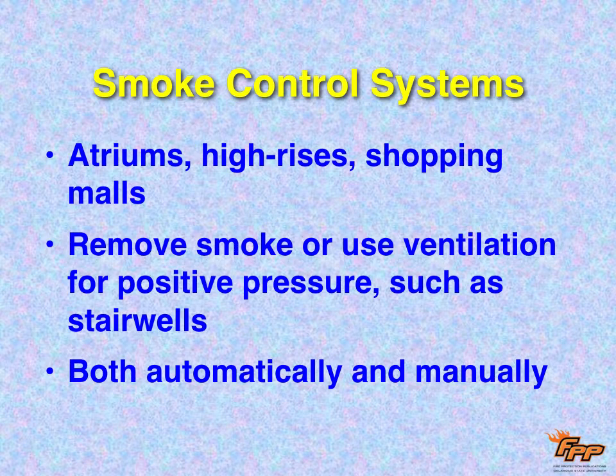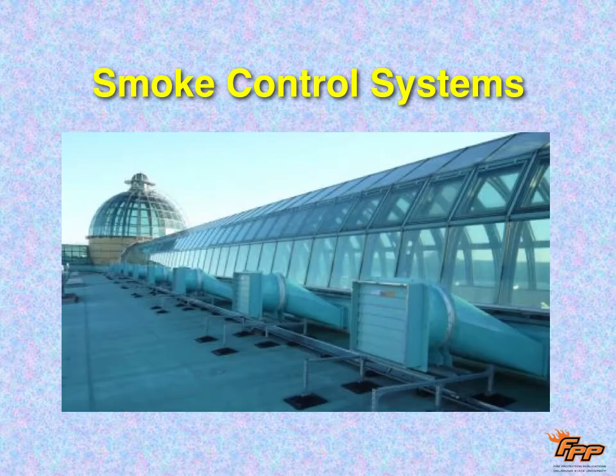So with smoke control systems, we are going to either remove the smoke, or we're going to put positive pressure, put fresh air into a stairwell or something like that, where we push clean air in to keep the smoke out and to keep people breathing. There are automatic and manual. Most of them are automatic with a manual. Manual systems aren't as reliable as an automatic system, so most of the time you're going to see automatic.